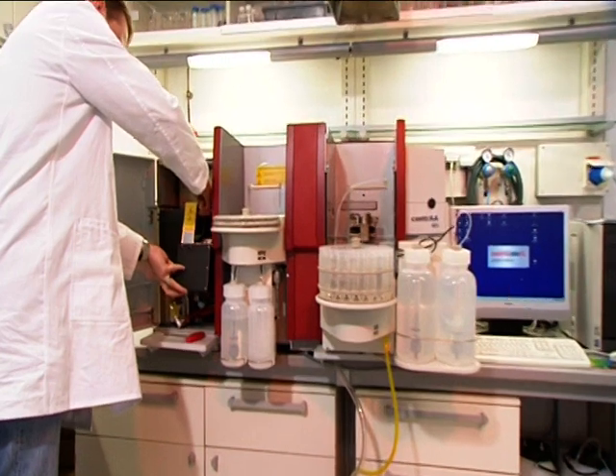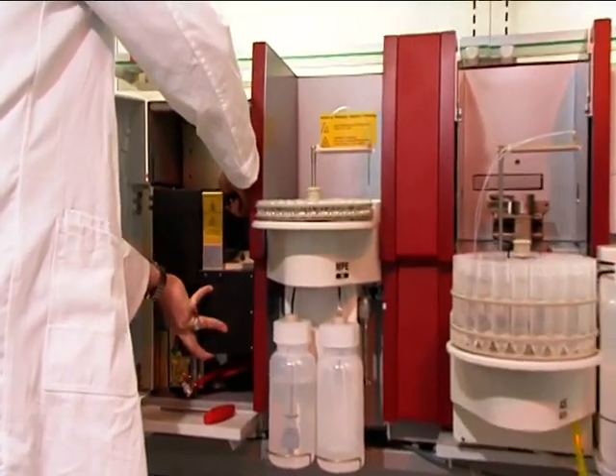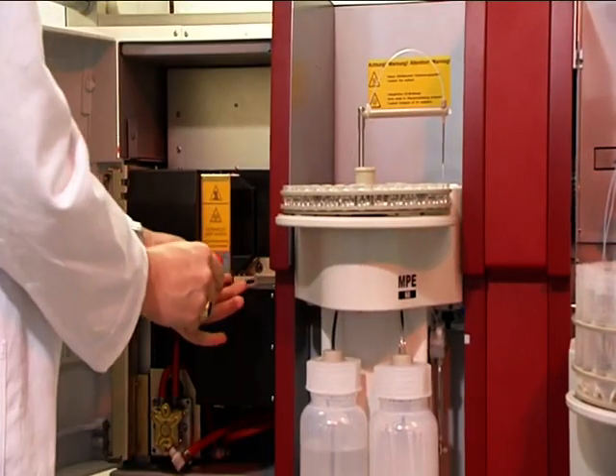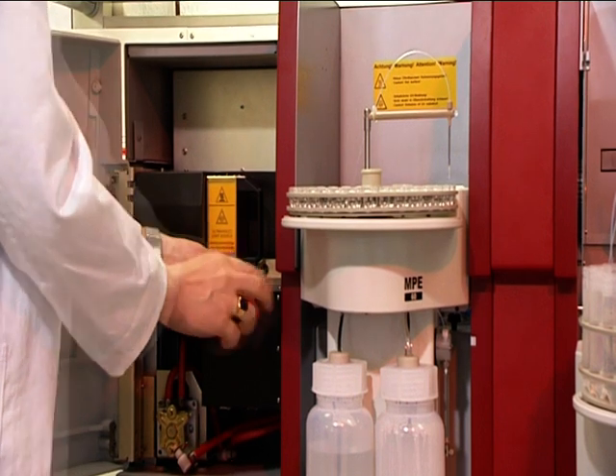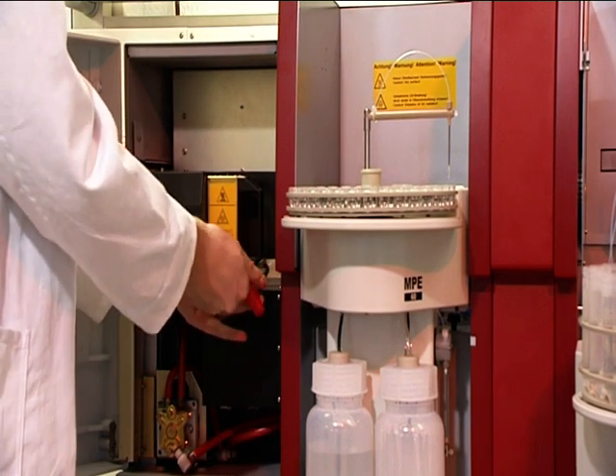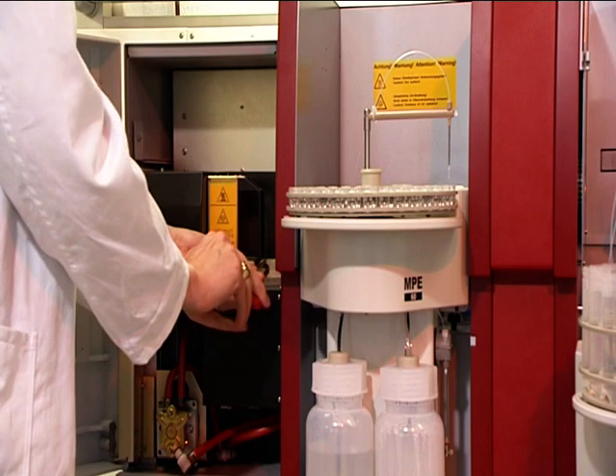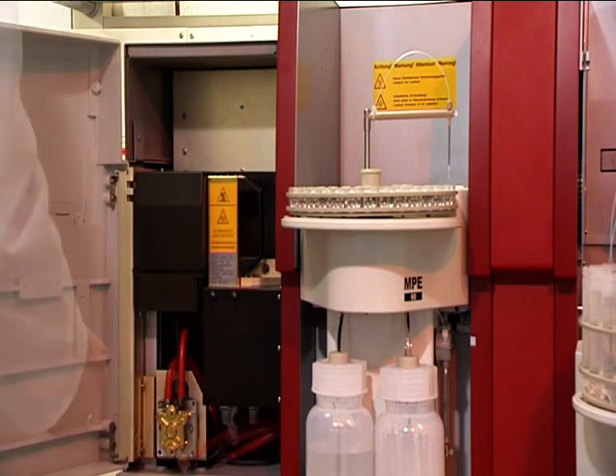Preparation time is reduced to a minimum since the xenon lamp is ready for use immediately, even for additional absorption wavelengths which cannot be measured with hollow cathode lamps. The lamp is applied fully adjusted in a housing. It can be exchanged easily with only a few manipulations.